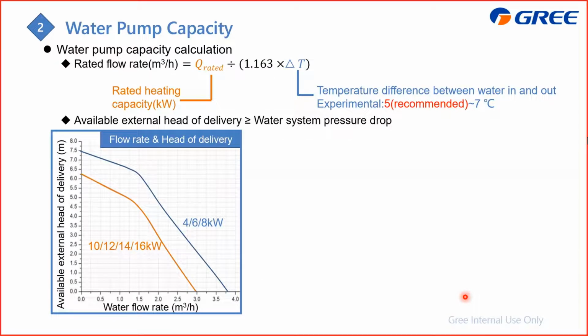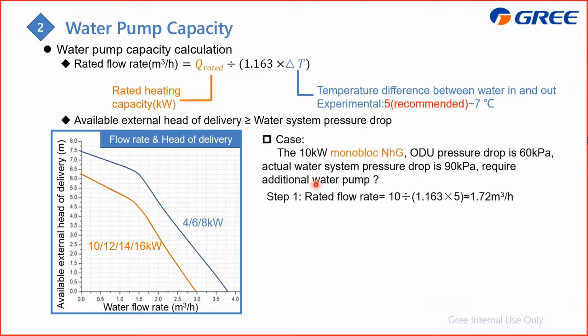And the first step is to select the water pump. Although we have one inside, if it is not enough, you also need to add another one. Just follow the formula, which is this one. This is the rated flow rate, according to the capacity of the outdoor unit. And this is the delta T, the temperature difference between the water in and out of the heat exchanger, and the experimental value is 5 to 7. The water pump already considers the pressure of the heat exchanger, including the outdoor unit and the indoor unit for that part. We also offer you this graph, the water pump graph. You can also check it.